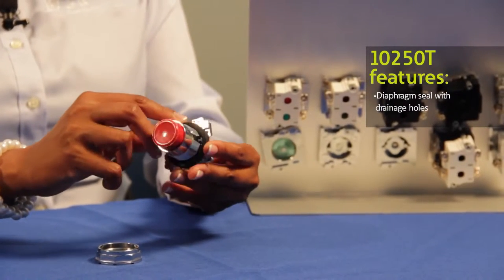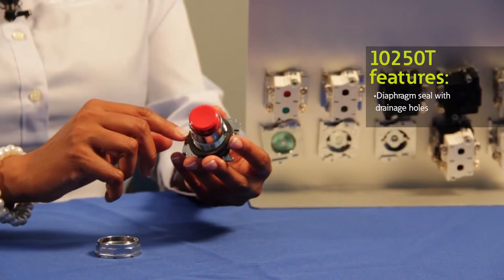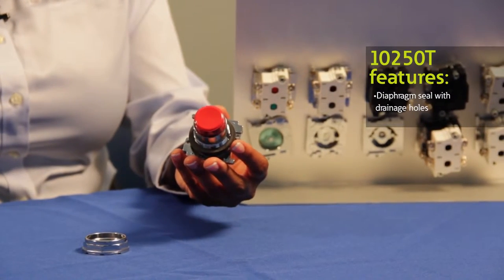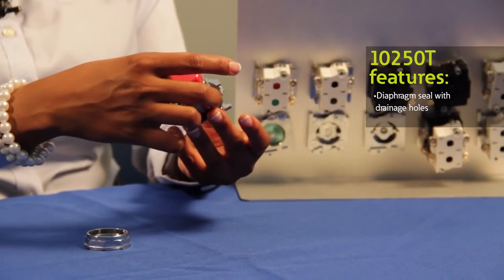Our 10250T operators also come with a diaphragm seal and drainage holes, which are unique to Eaton. The diaphragm seals prevent buildup of liquid inside the operator, especially in freezing conditions. And the drainage hole protects the operator by draining liquid, which is a great feature for high-pressure washdowns.